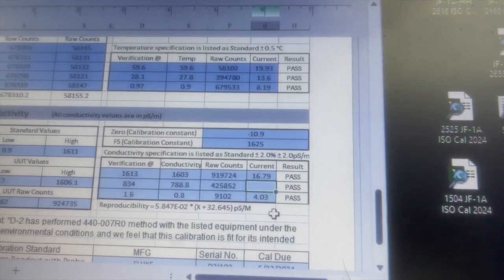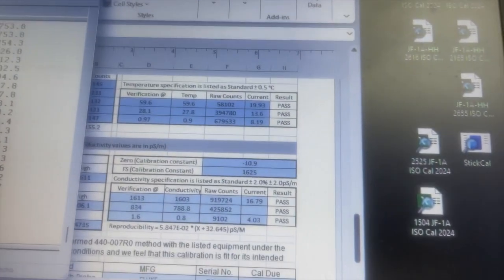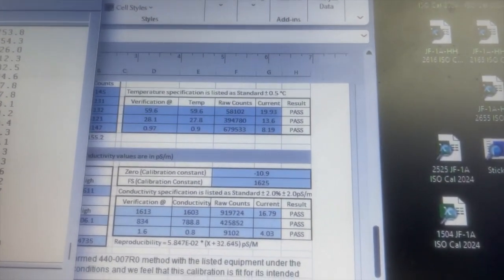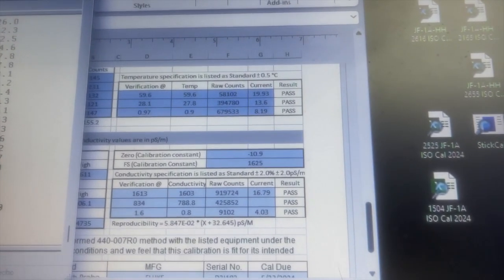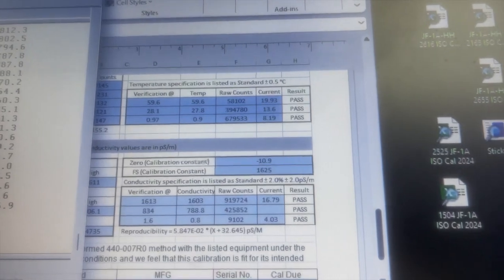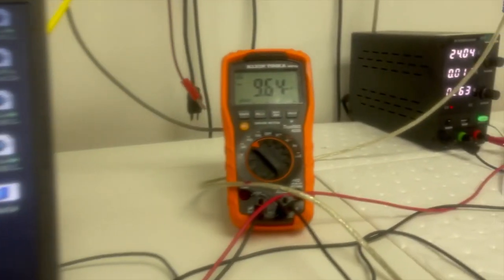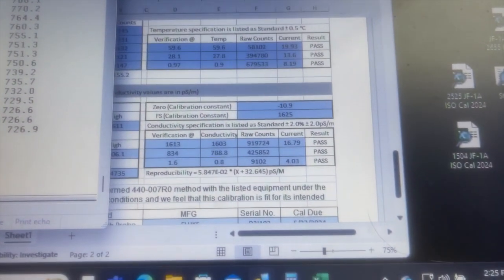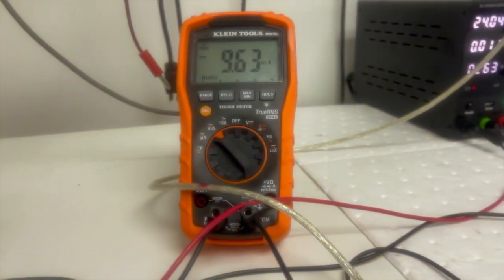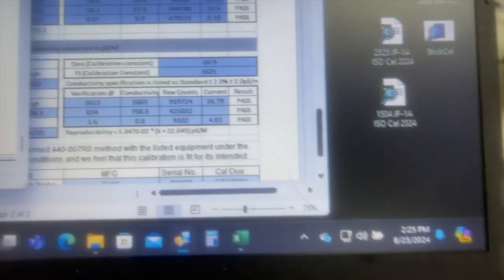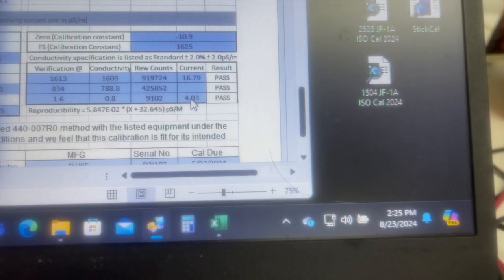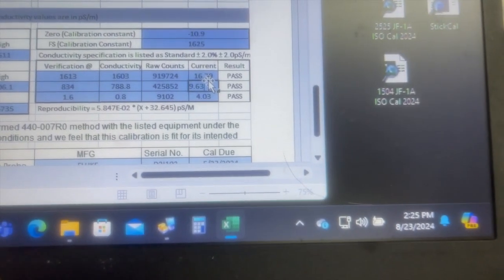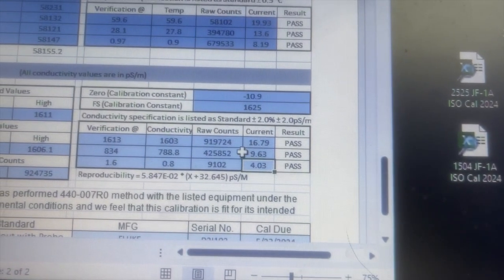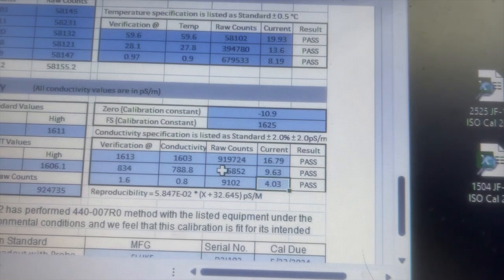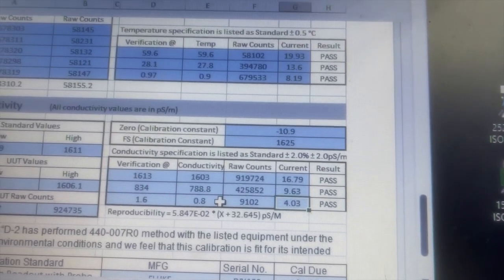And our raw counts were 425,852. And then once we go into run mode, we have to get our voltage. The voltage is 9.63, which is right where it should be. And you can see now we have passed the conductivity, calibration, and verification.